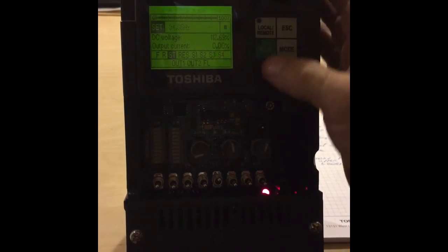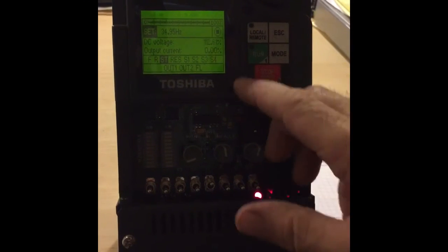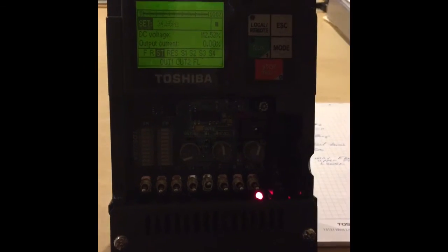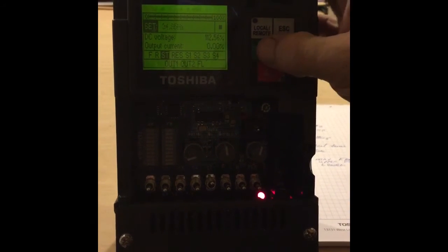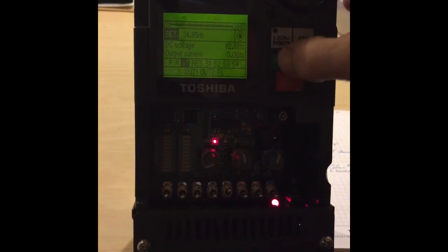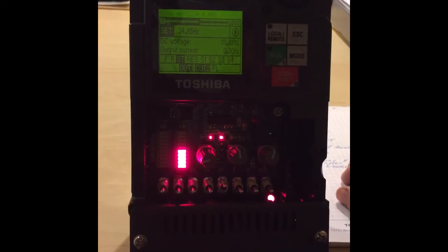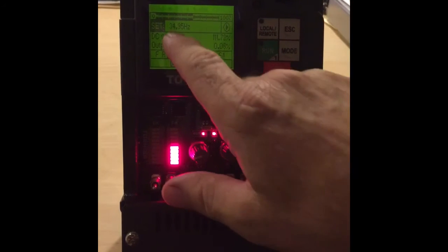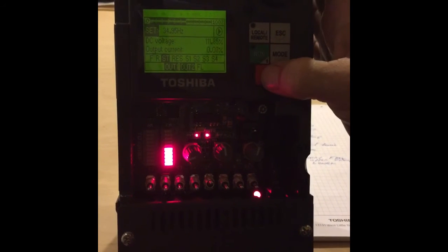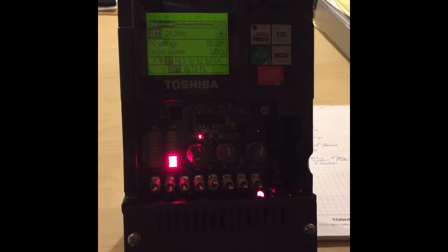Also, something else I wanted to teach you is you have a local and remote button. If you push the local button or the remote button, it tells you right here whether it's being used or not. And then if I set my upper limit to run, and then change my hertz, the drive takes off and runs. I just randomly had it set at 34.95 hertz. The drive will, in 6 seconds, get up to 34.9 hertz. If I want to stop that, I hit the stop button. The drive decelerates down to, I think that was 22 seconds on the deceleration time.